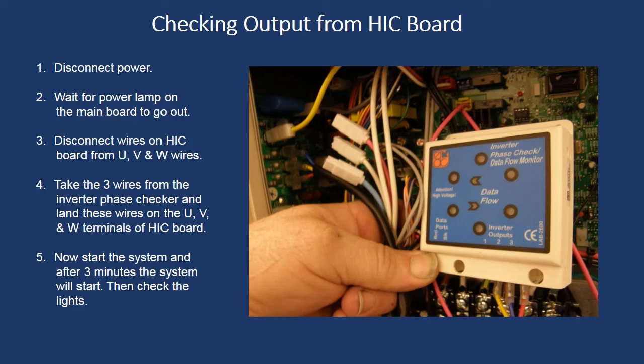When checking the output from the HIC board to the compressor, first disconnect the red, white, and blue wire from the HIC board. Next, take the 3 wires from the inverter phase checker supplied with the tool and land each wire onto the U, V, and W terminals. It does not matter in which order these wires are landed.